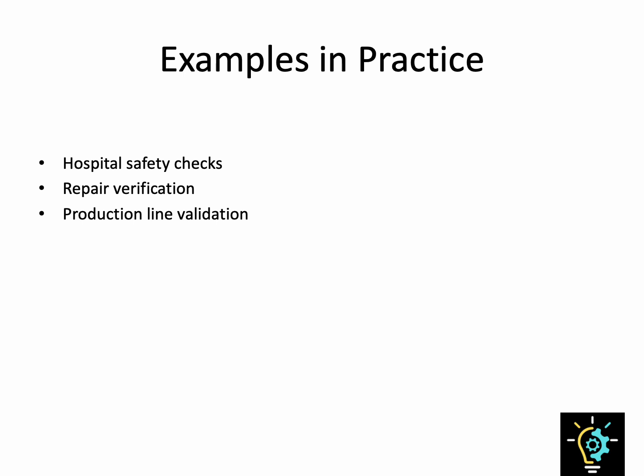Manufacturers are also increasingly applying IEC 62353 at the production line stage. So the baseline measurement hospitals can take later can be directly compared with the factory results. And any discrepancies or drift in the leakage current become immediately visible. And what's the purpose of this? It creates a chain of safety checks from the factory to the front line, which is the hospitals and the clinics. And rental companies can rely on these tests before shipping a device to a hospital. So it creates a reference.